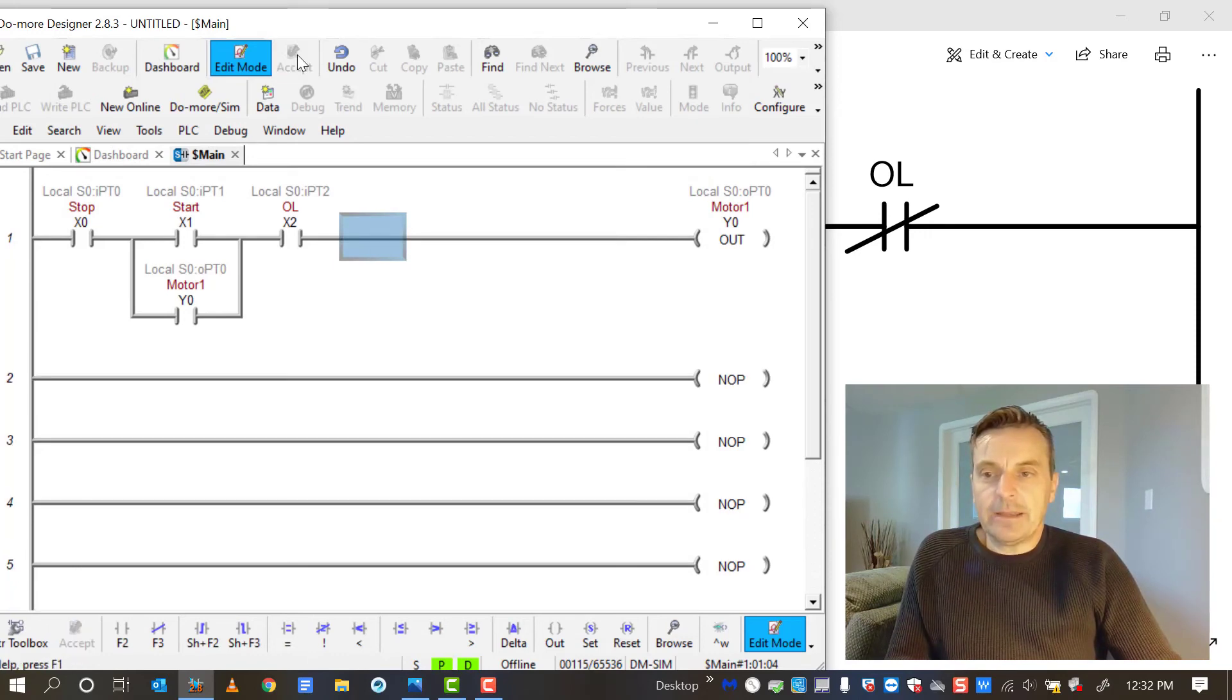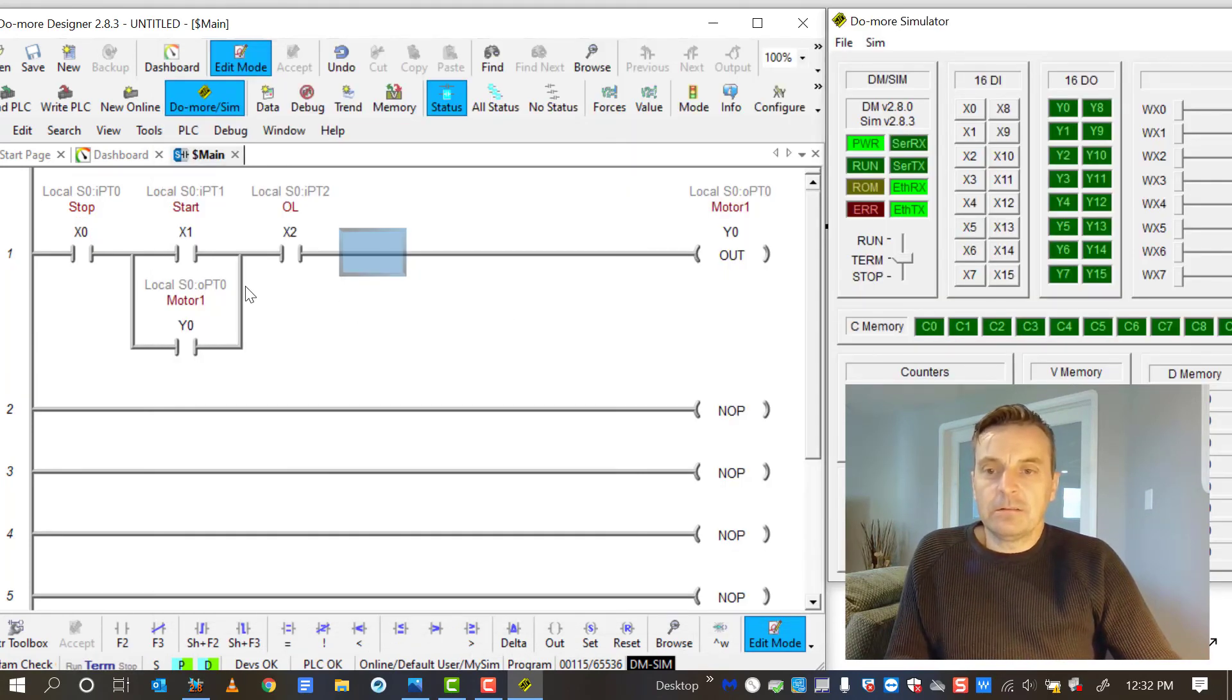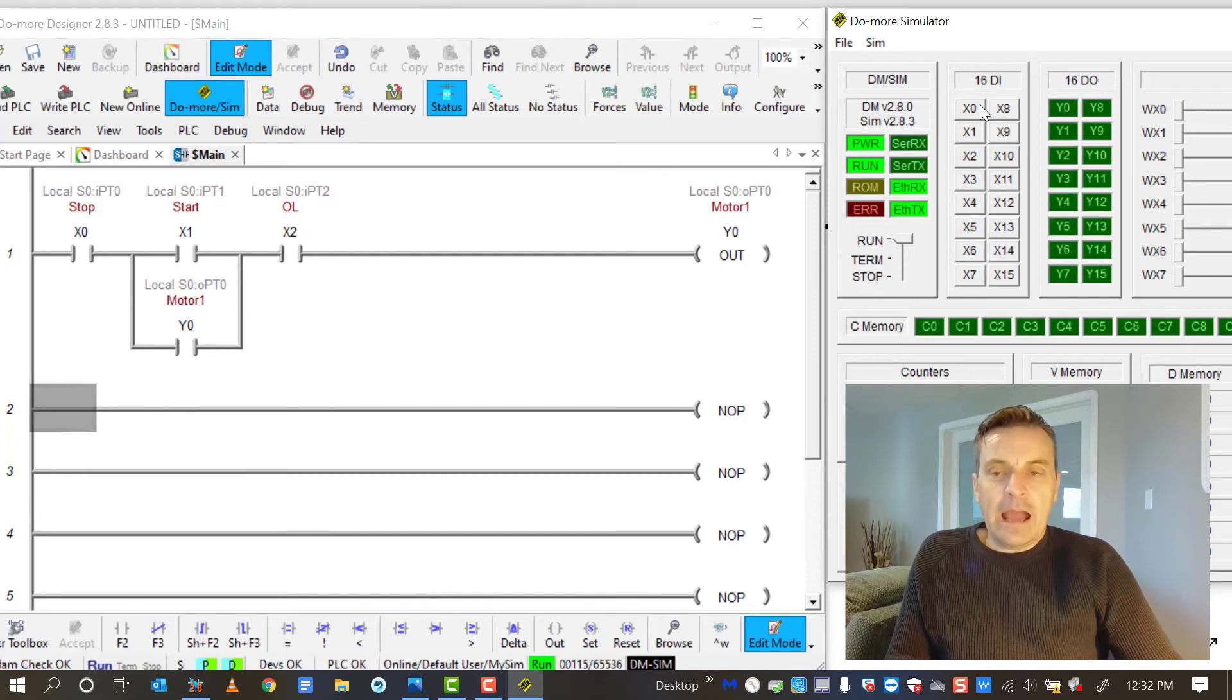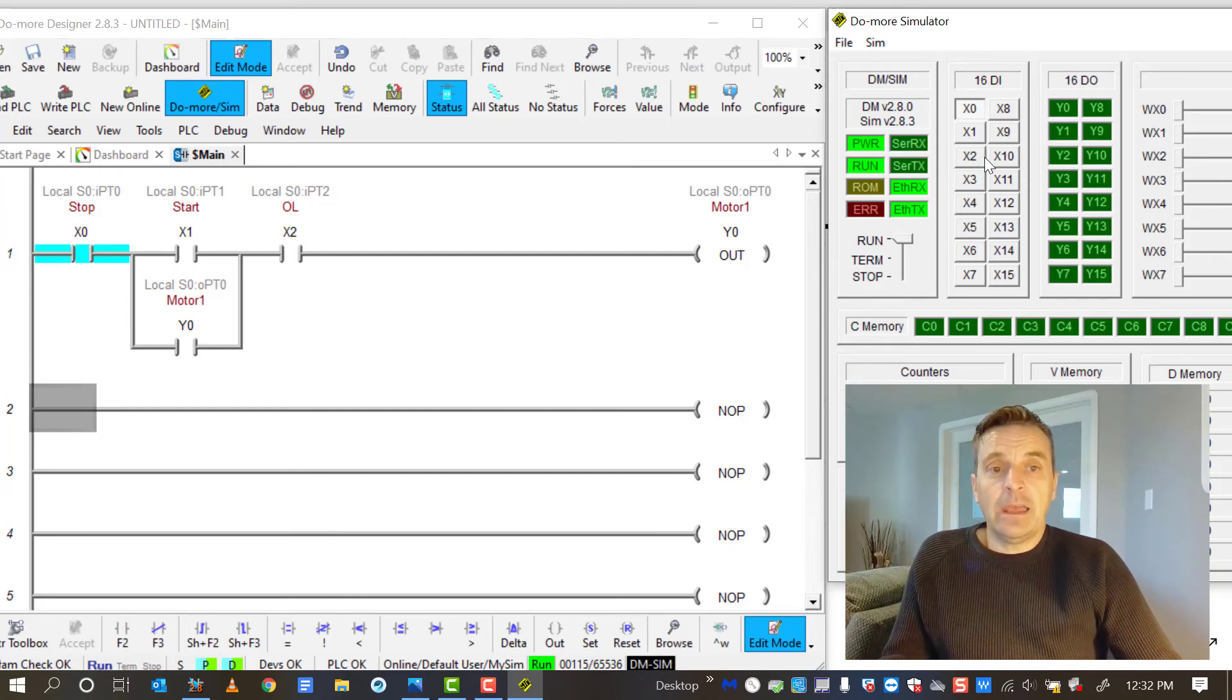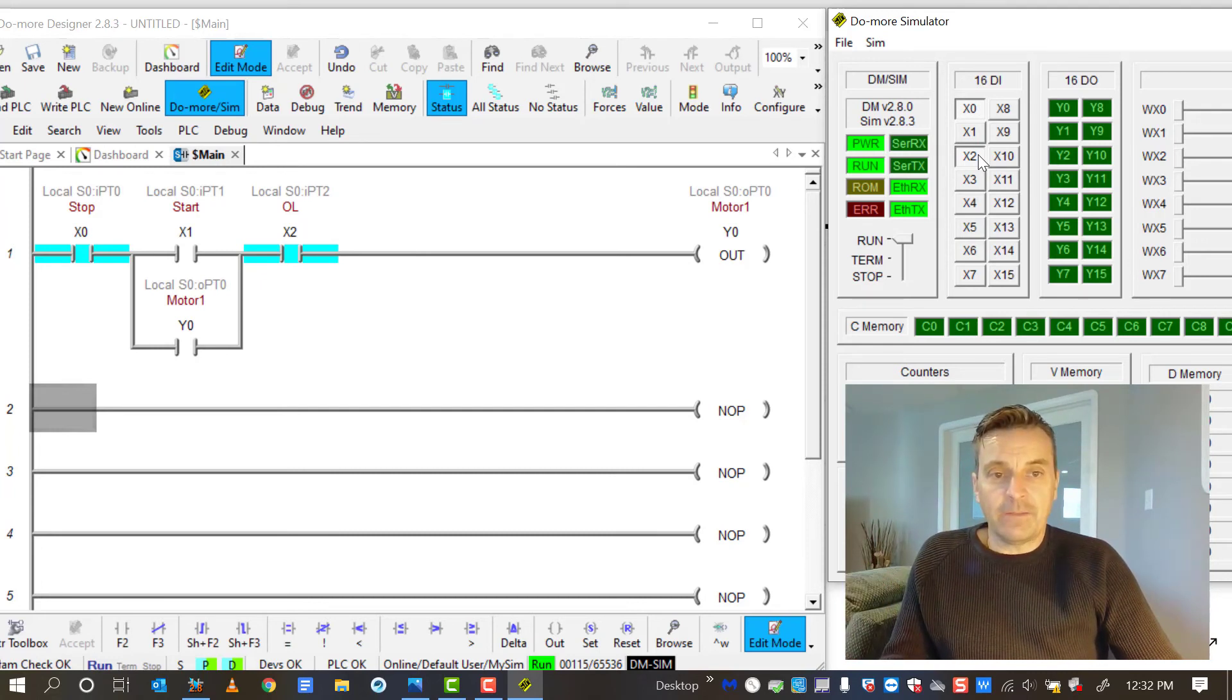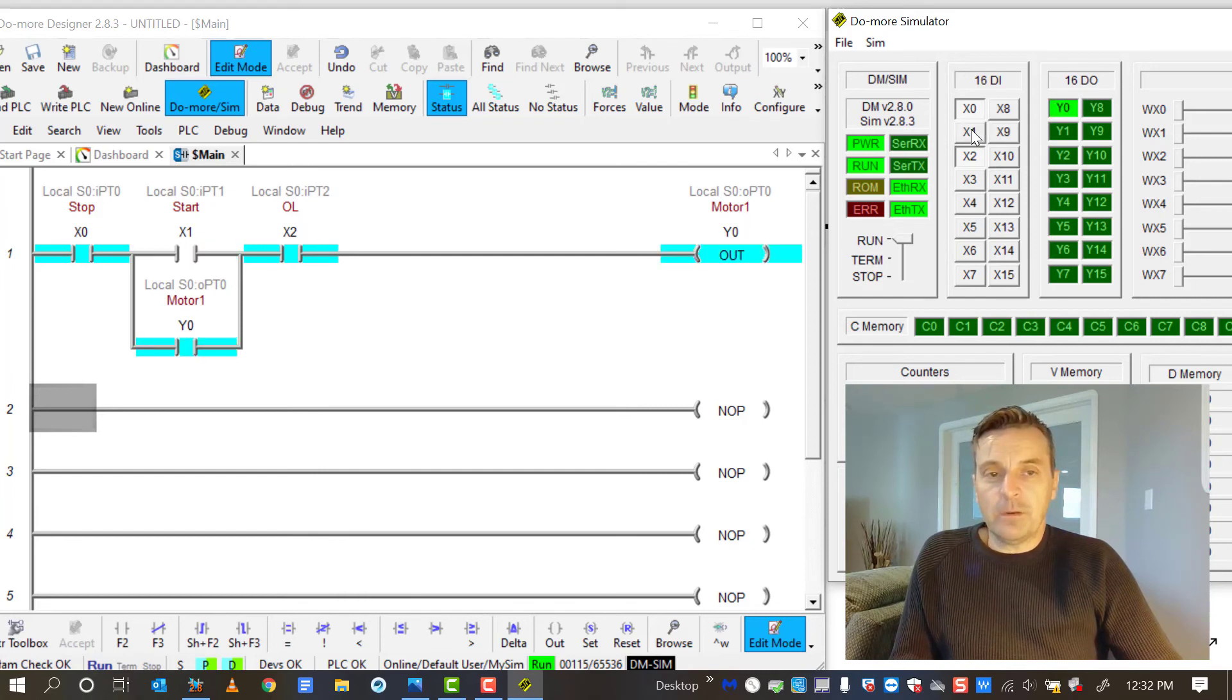So now let's accept those rung edits and start my simulator. And now you can see that nothing went turquoise there. There's no highlighting there, so nothing is ready to go. Put it into run. And now I'll close X0 to simulate a closed button in the field. And I will close X2 to simulate a normally closed contact at the motor starter. Now those are closed like they would be out in the field.